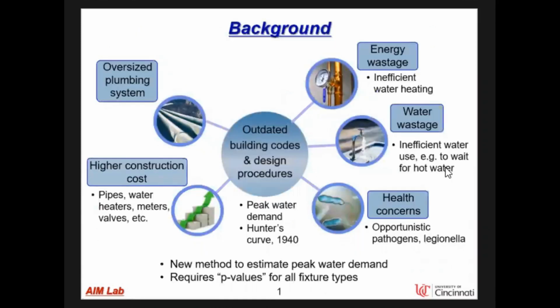So the peak water demand estimation is of utmost importance when designing a premise plumbing system for a new building, as it governs the size and cost of the entire water supply system. The traditional method for the estimation, called the Hunter's curve, was developed in 1940 and has become outdated with the broad adoption of water efficient fixtures. This leads to significantly overestimated peak water demand and thus oversized plumbing systems.